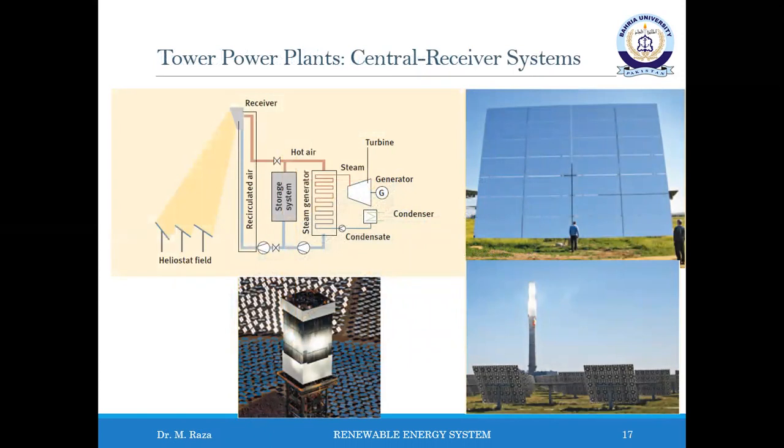Solar tower power plants belong to the point focus systems. A feature of this system is that the direct solar radiation is concentrated on a single spot, the focal point. Considerably higher concentration factors can be achieved than with the line focus system, which means that the optimum operating temperature in the receiver can also be increased. This enables power plant processes to be coupled with better process parameters and thus greater efficiency. This in turn leads to higher overall efficiency when transforming solar radiation into electricity, resulting in potentially lower electricity generation cost.